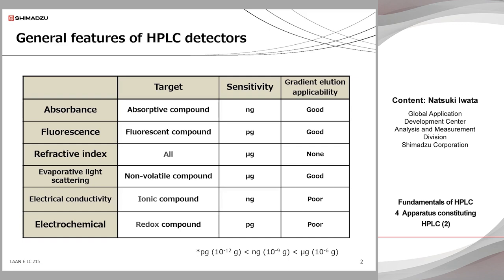Compounds having conjugated double bonds or aromatic rings show high response on the absorbance detector. In general, selective detectors, which can be applied to limited target compounds, tend to show high sensitivity. Some UV absorbance compounds provide luminescence phenomena at particular wavelengths, and they are detected by a fluorescence detector that affords generally higher sensitivity than that of the UV detector. On the other hand, a refractive index detector — so-called RID — has wide versatility, covering saturated hydrocarbons and saccharides that have no UV absorption. Generally, the sensitivity of RID affords rather worse sensitivity compared to that of the UV detector. Furthermore, it cannot be employed with gradient elution due to large baseline drifting caused by varying mobile phase composition during analysis.